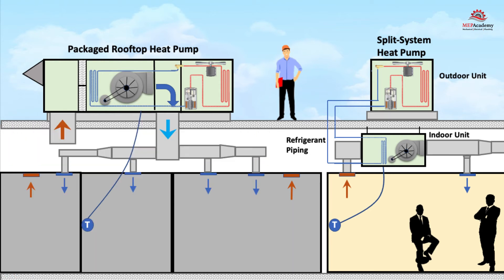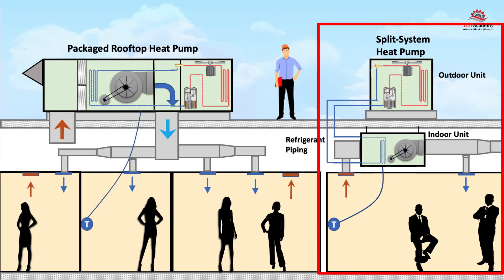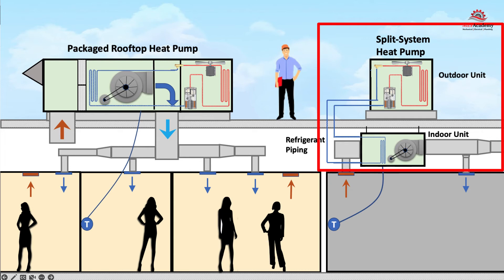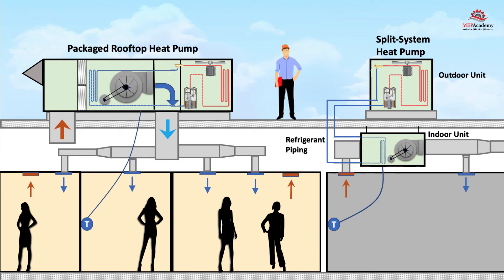There may be spaces within the building that operate only on specific days of the week. If this space is on the same system as the regularly scheduled equipment, it might pay off to provide a separate system or method of controlling the conditioning of this space. Working with the optimal start to determine the best time to start the equipment, including night setback temperatures, this strategy ensures the equipment is only running when the building is occupied.